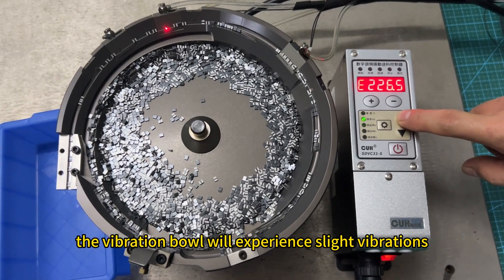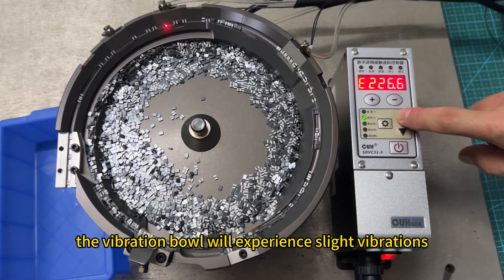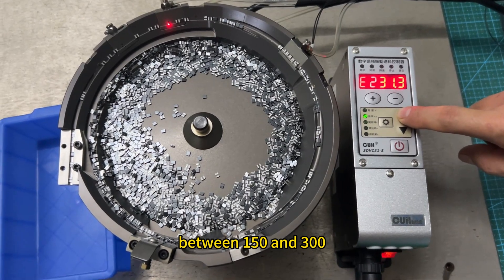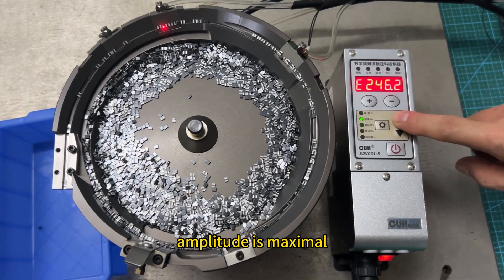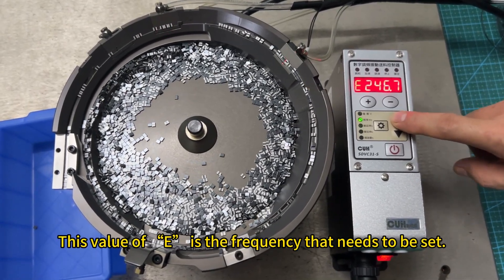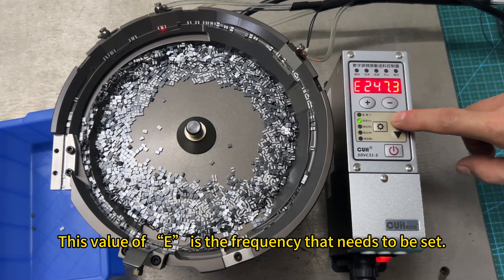The vibration bowl will experience slight vibrations. Between 150 and 300, there will be a value where the vibration amplitude is maximal. This value of E is the frequency that needs to be set.